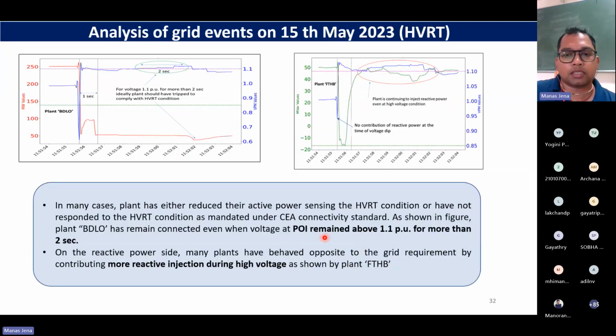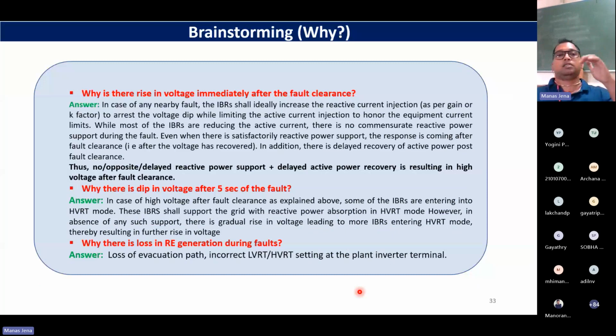So even if it is above 1.1 for more than 2 seconds, it is still there. On the reactive power side, many plants have behaved opposite to the grid code requirement by contributing more reactive power injection during high voltage. It is like a crime, isn't it? This 1.1, you can see this blue color is more than 1.1, and this particular plant is actually injecting reactive power, isn't it? So essentially, maybe some issue with the controller, it is actually acting in an opposite way to what was expected.